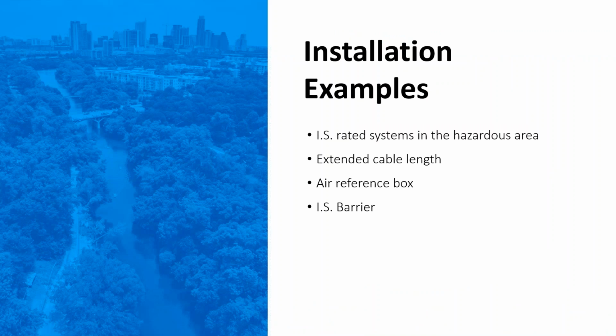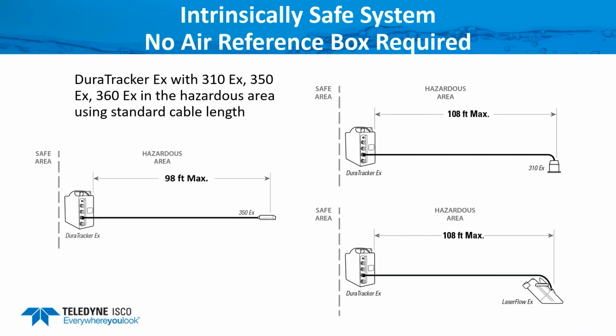Now let's cover a couple of installation examples. I'm going to cover the intrinsically safe rated system within the hazardous area, what you can do if you need to extend your cable length, if an air reference box is used, and when you use the IS barrier. First, let's look at where the entire intrinsically safe system is within the hazardous area. As you'll notice, there's no air reference box needed. The ultrasonic sensor and laser flow sensor have a maximum of 108 feet of cable for standard lengths. So the entire system will be mounted in the classified area, and the 350EX has a maximum cable length of 98 feet. But again, all this can just be set in the manhole, and you'll have a modem on there so you can call it if you need to.